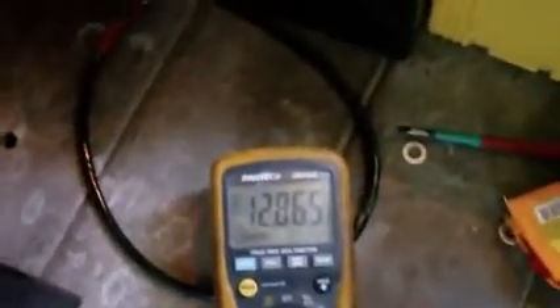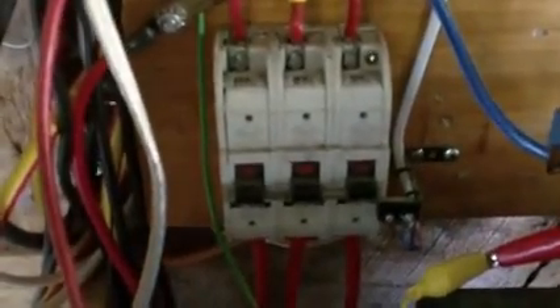Sitting at 12.86 at the moment. There's no loads being drawn, they're not being charged. So now when I throw the switch... okay, we're in there. It briefly went into full voltage sensitive relay override, but then it went back to regulation almost straight away. There we go.